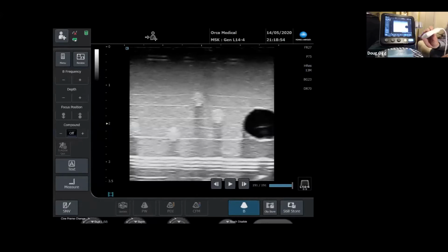Yeah, in my experience, for a good test you need two different types of phantom. One is what's known as a resolution phantom, which tests the resolution of the system. But perhaps more important, and you can see it on the image I've got frozen here, is contrast resolution. In other words, the ability to pick up a difference in echo texture between structures. That is really, really important, and it can get very, very subtle.